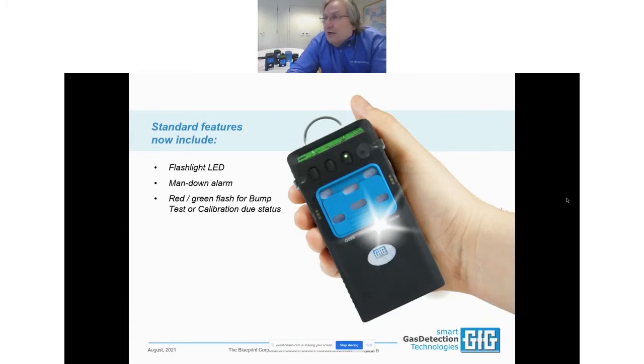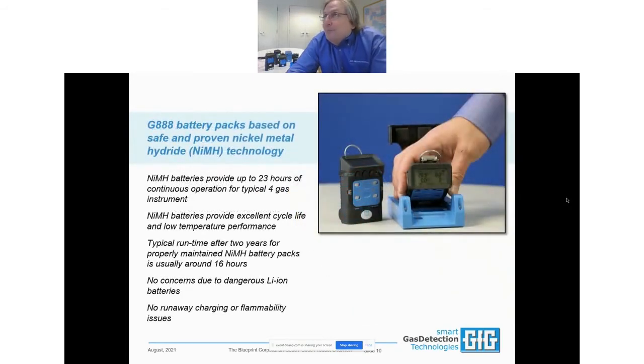We also include a little helpful hint as to whether the instrument is in calibration or in bump check, if you've specified you want a reminder for that. If it's time to do something, you'll get a red flash once a minute. If it's all good to go, you'll get a little green flash once per minute. So you have knowledge without even having to look at the display and check the most recent calibration or bump test dates. The G888, I can't stress the importance of our rechargeable battery technology.